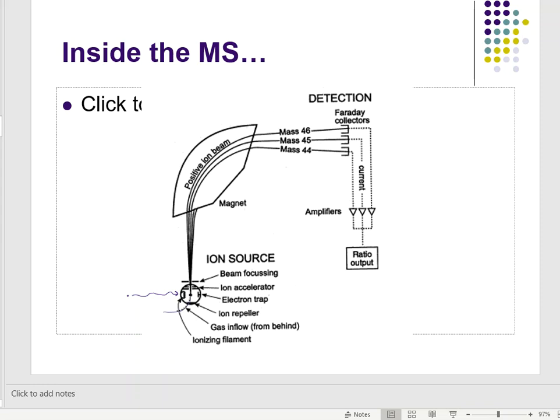And we're getting some gas flow. Some gas flow is coming from the instrument because we've got to keep this thing pumping full of gas. Typically, this gas flow is going to be helium. So the helium is getting mixed into that chamber with my compounds, and then this molecule is going to go through an electron beam. So the ionizing filament.